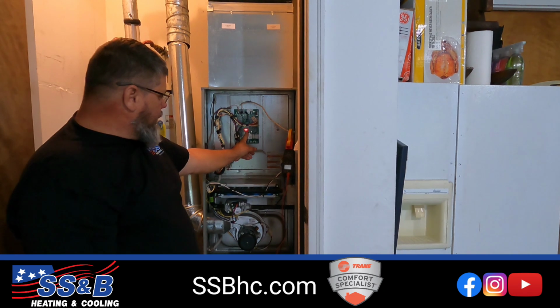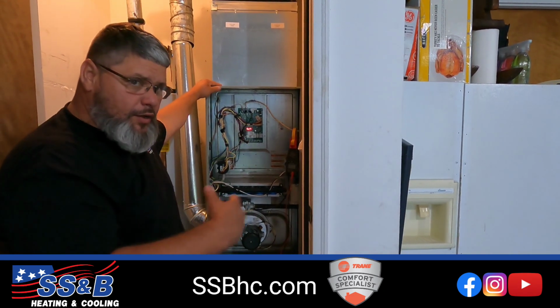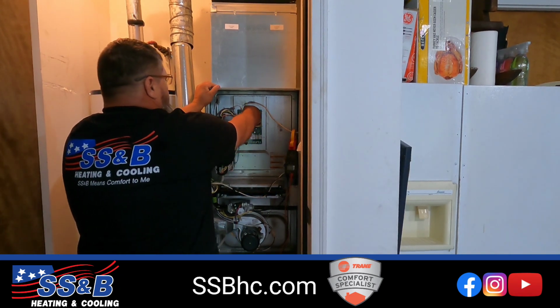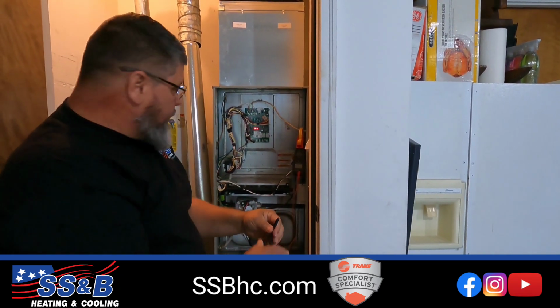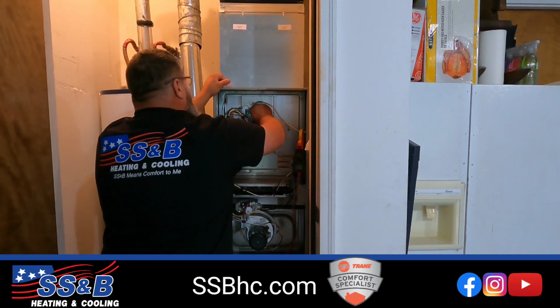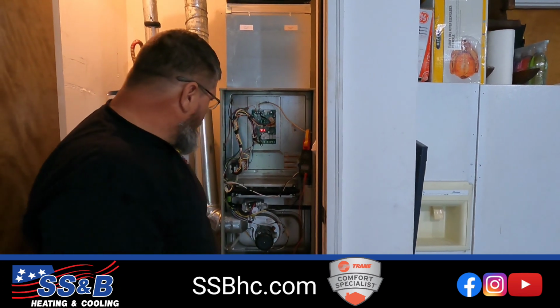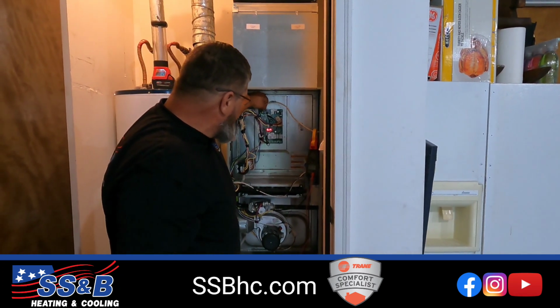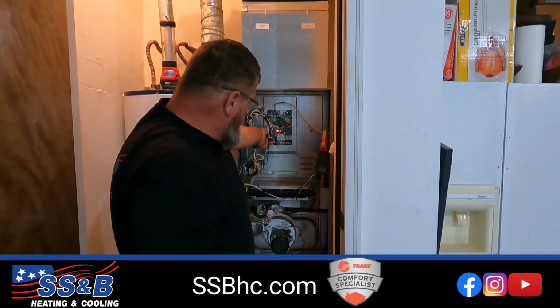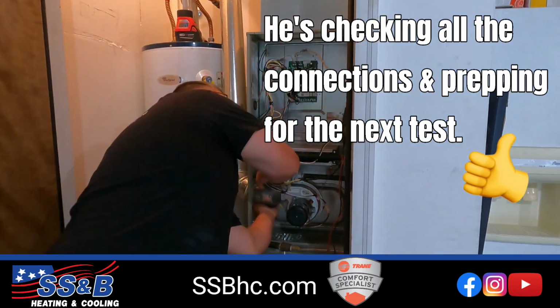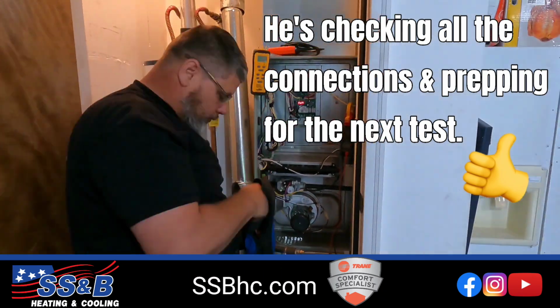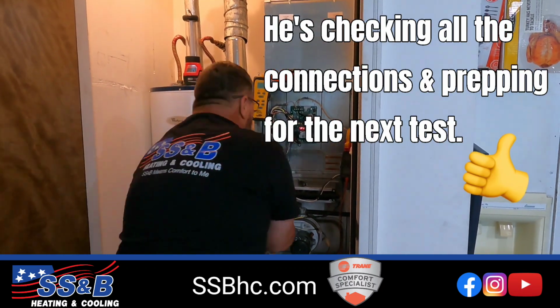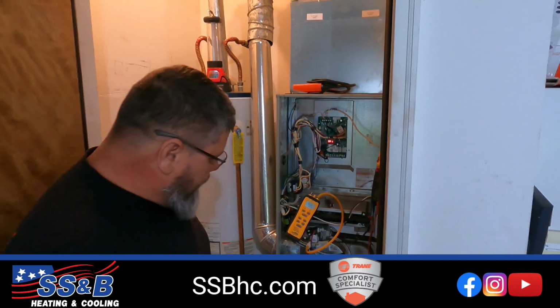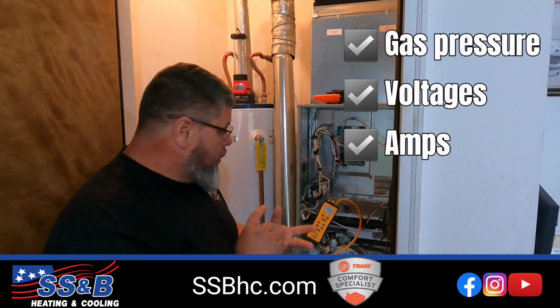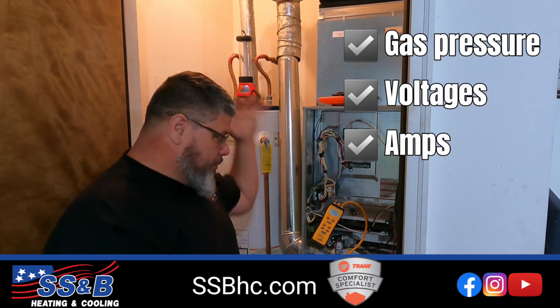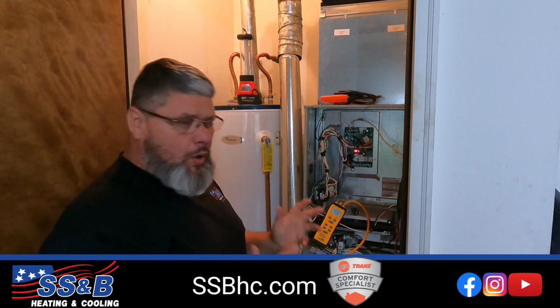All right, so the control board says now that the heat is on and the blower is actually running, so that is a complete cycle. At which point we can now start actually testing and checking everything to make sure it's working correctly. One thing we do is we always check wires to make sure that we have a good connection, no loose connections. All right, from here we're actually set up now to where we can do the gas pressure. We can do all the voltages and amp draws at this one time. So basically we can go through the whole entire system all at one time.